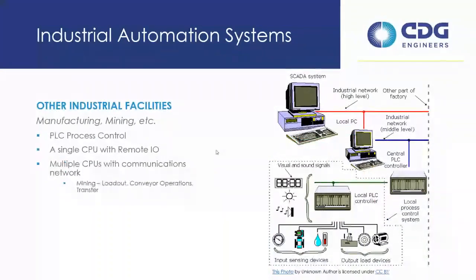The last one I got is for other industrial type facilities. So manufacturing, mining, maybe more of a heavy kind of commercial type facility. These are most likely going to be PLC control systems. DCSs have a high cost to entry, but with PLCs, there's a lot more variety, and the costs can vary from manufacturer to manufacturer. So you'll see this in places that may only have a few hundred I/O points. You'll almost always see a PLC type system. You can have a single CPU with remote I/O that controls the whole process. You can have multiple CPUs that can communicate over a network, Ethernet, Modbus, fiber, any kind of various protocol or hardline or fiber or radio type deal. So we'll see it a lot.